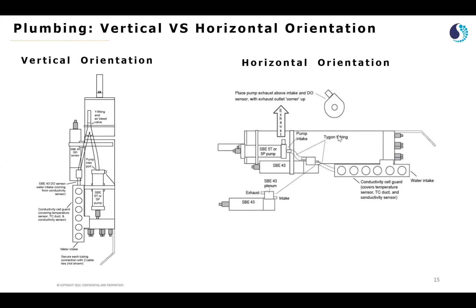Now that we've been through a lot of physical overview of the SBE 19 plus V2, I'll be talking very specifically about the vertical orientation deployment in this system, and very specifically about how the plumbing fits. Right here, you have the conductivity cell, the Tygon tubing, and the Y fitting. It's important to note how it's in, and the air bleed is basically at one of the highest points of the instrument. And that's important because that's where all the bubbles are released from the whole system. And it's important for us to get rid of the bubbles so that we get high quality data during vertical deployment of SBE 19 plus V2.